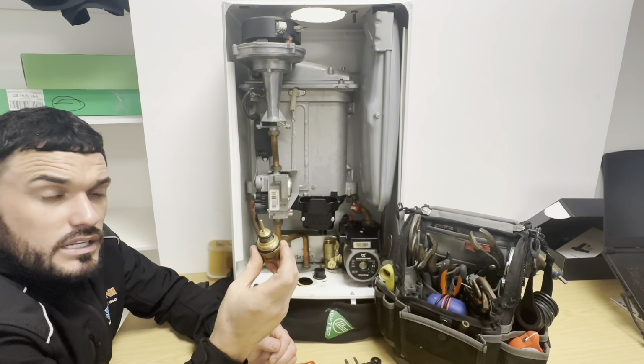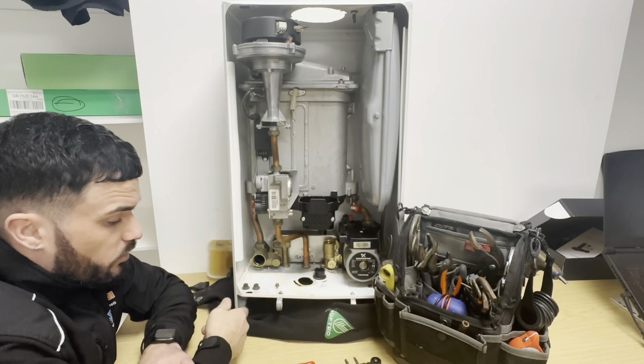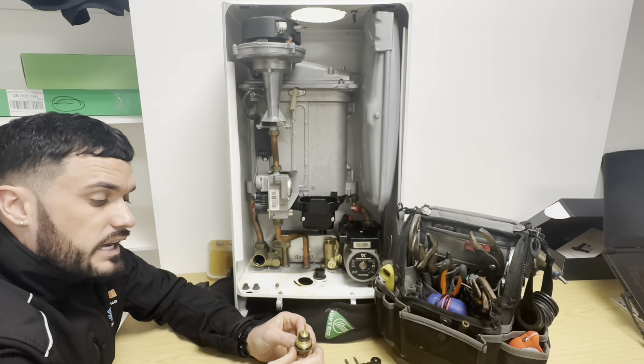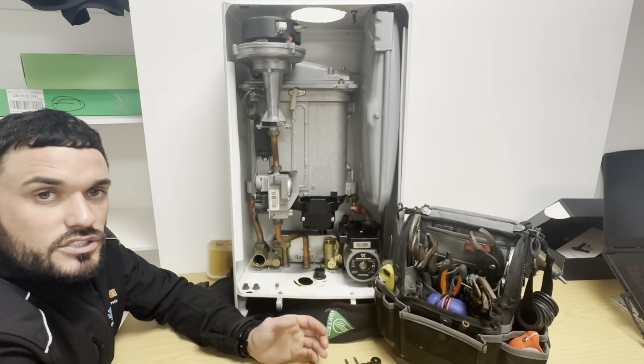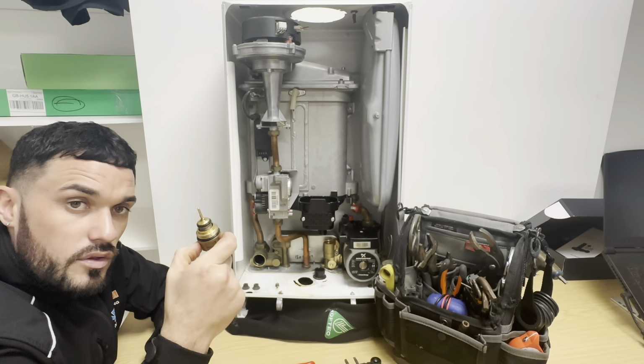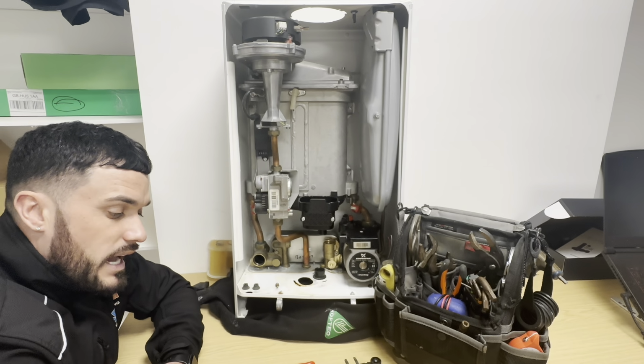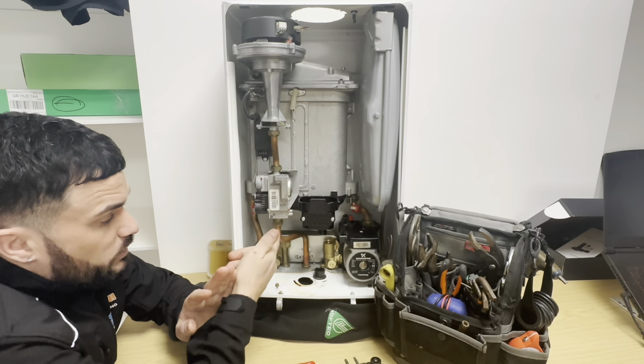If it's your diverter valve, always feel for the flow on the heating pipe, basically. So your flow on the boiler, in hot water mode, if you're getting heated water going down the flow on the radiators, you know, if you get a bath and the bath starts getting warm, it's a telltale sign, like I said, that the diverter valve has gone. When the diverter valve goes, that could also be forced to die, basically come to its end of life, with the plate heat exchanger being blocked.